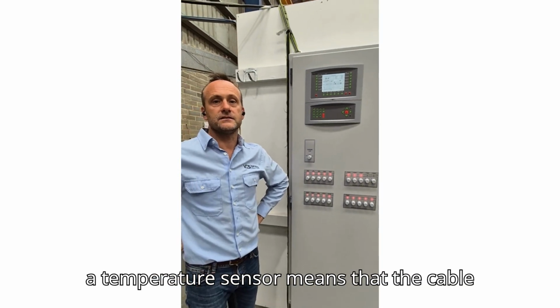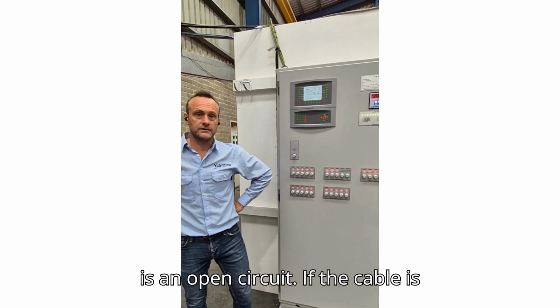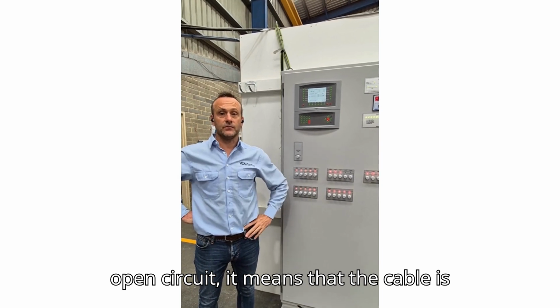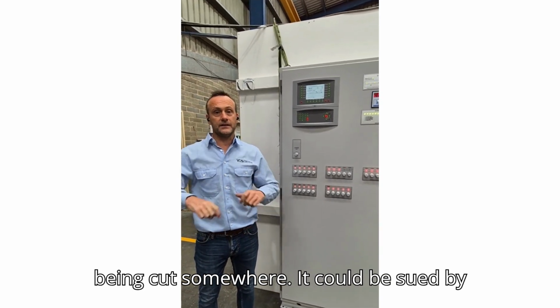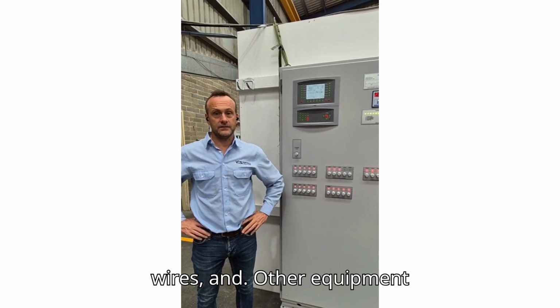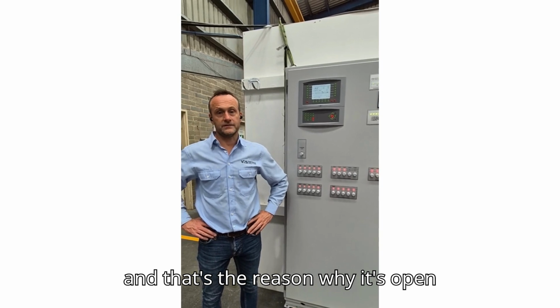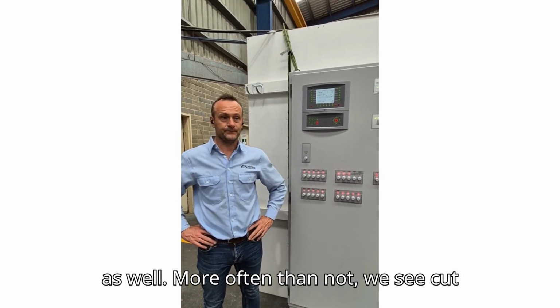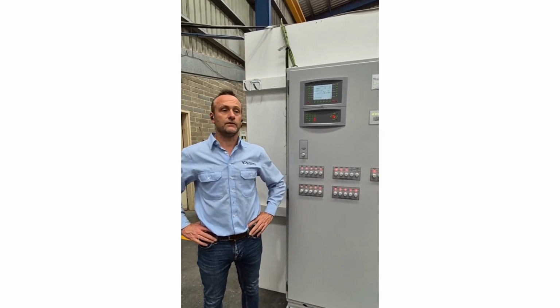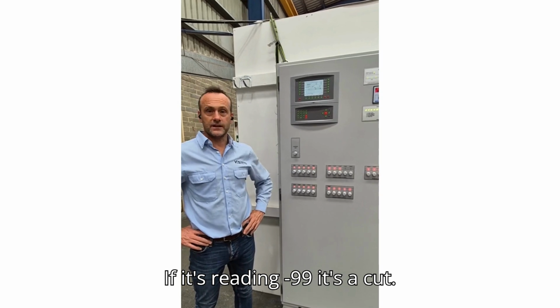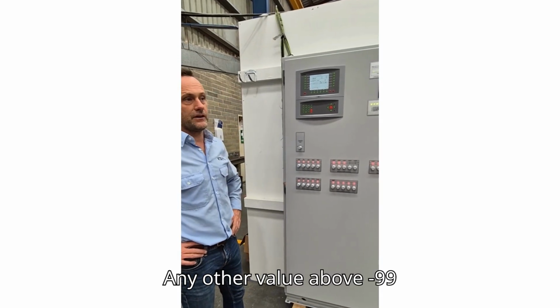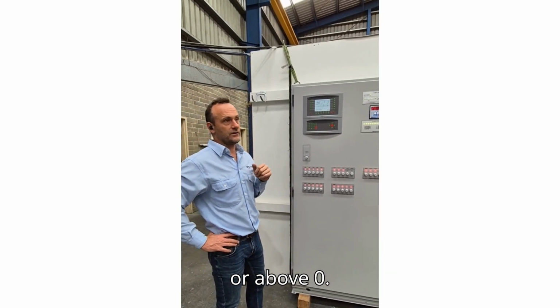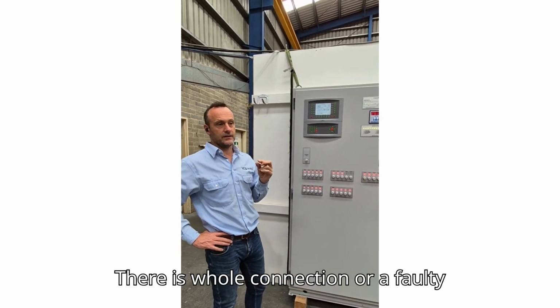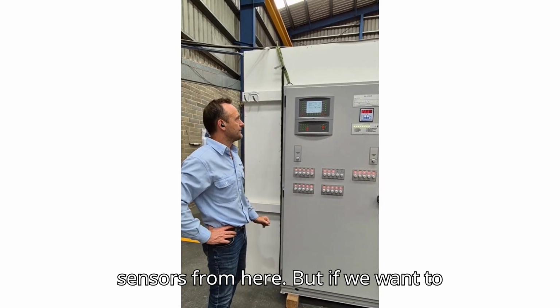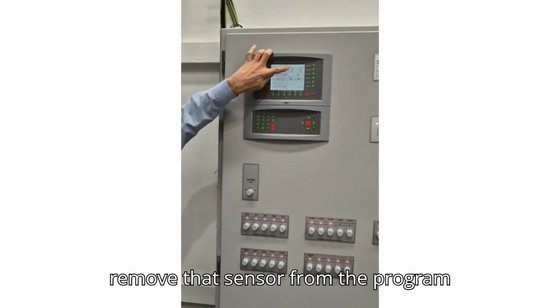Minus 99 on a temperature sensor means that the cable is open circuit. If the cable is open circuit, it means that the cable's been cut somewhere. It could be chewed by a rat, it could be rubbing against guy wires and other equipment, and that's the reason why it's open circuit. It could be a bad connection as well. More often than not, we see cut cables in the field from general wear and tear. If it's reading minus 99, it's a cut. Any other value above minus 99 or above 0 generally means that there is a poor connection or a faulty sensor itself.